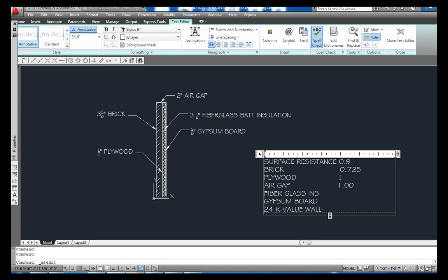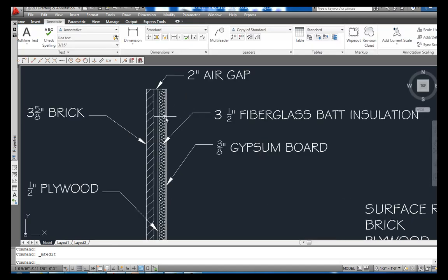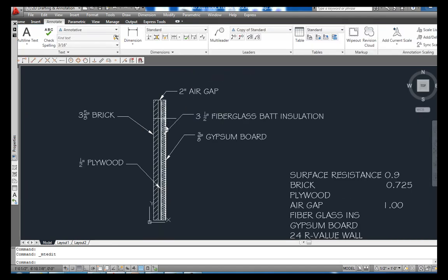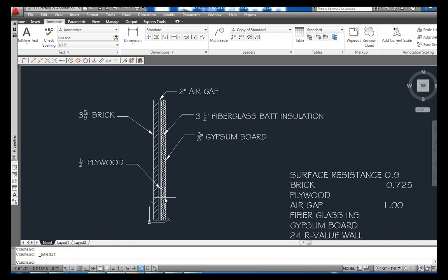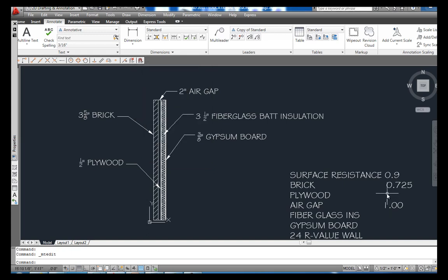And jump back up here, I'll get my plywood next. My plywood is one half of an inch, and look at my chart, it's under softwoods and plywoods, 0.9. So we're just going to take our plywood that's a half of an inch, 0.5, and times it by 0.9, and then we're going to equal 0.45 on that one.